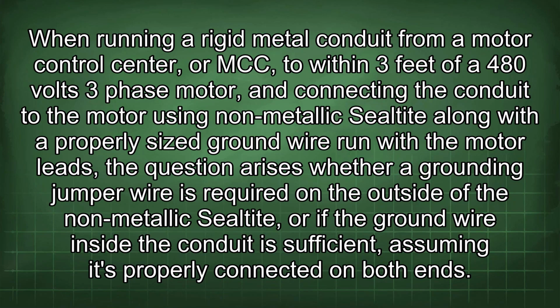When running a rigid metal conduit from a motor control center, or MCC, to within 3 feet of a 480 volts 3-phase motor, and connecting the conduit to the motor using non-metallic Sealtite along with a properly sized ground wire run with the motor leads, the question arises whether a grounding jumper wire is required on the outside of the non-metallic Sealtite, or if the ground wire inside the conduit is sufficient, assuming it's properly connected on both ends.